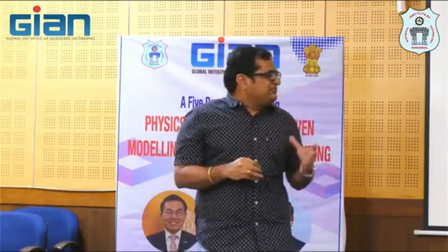Yes, it is possible. As far as FDA is concerned, they will say that it is a certified material, titanium 6-4 or cobalt chrome or 316L. But at the moment you process it, design it, print it and put it into the body, we need to follow that kind of thing. That's our experience, and I can say it should be foolproof, but it's not happening that way.